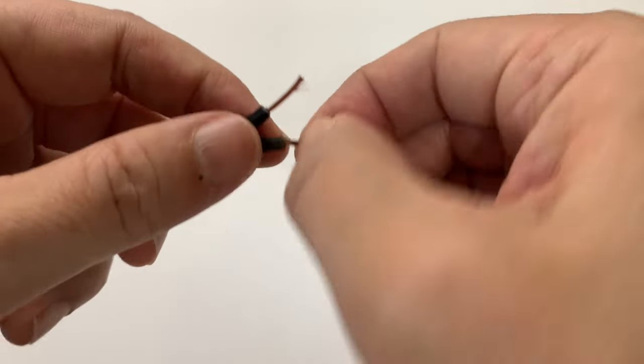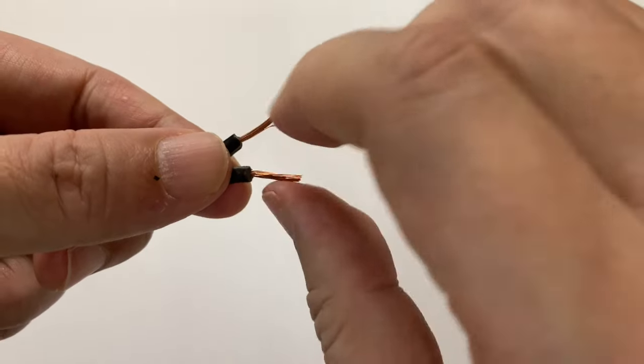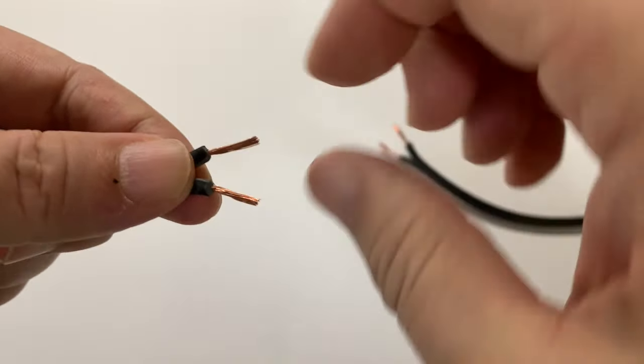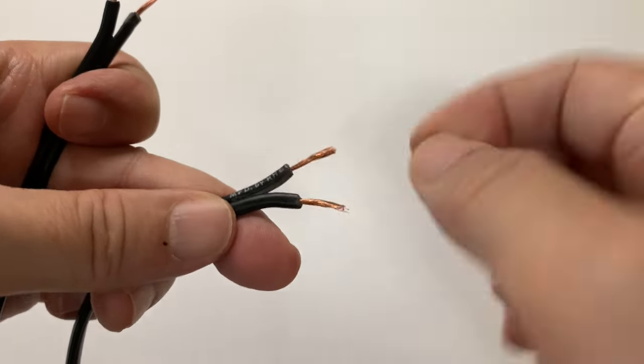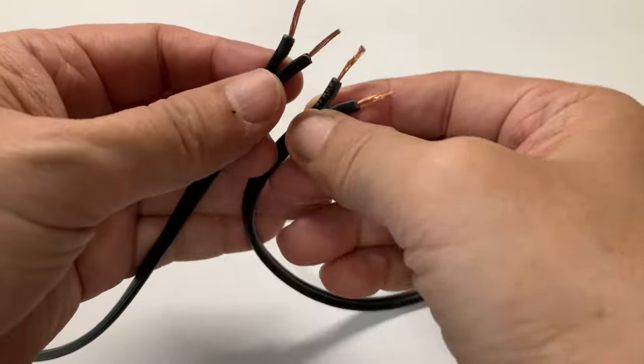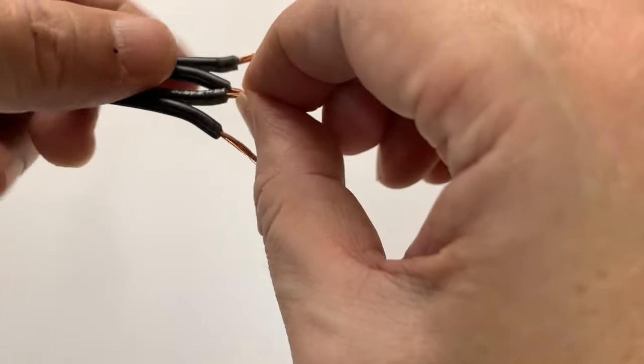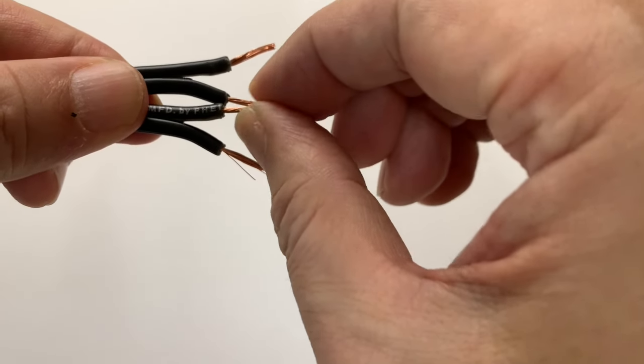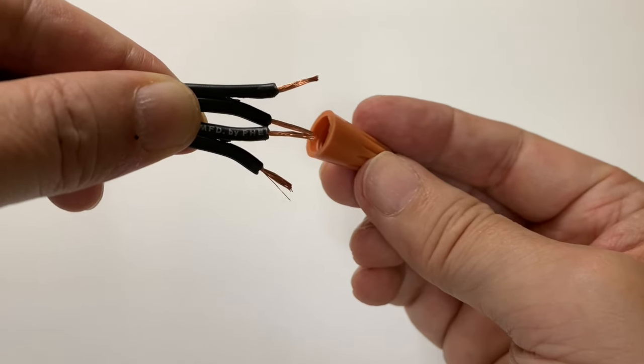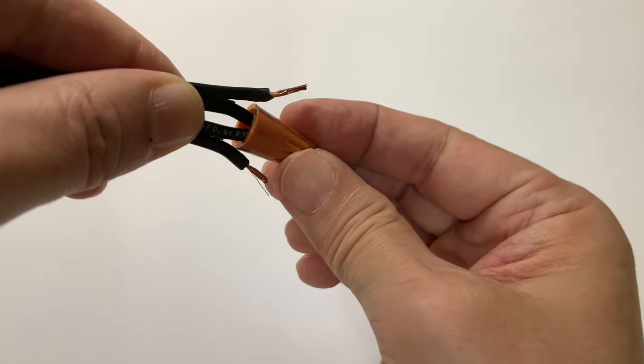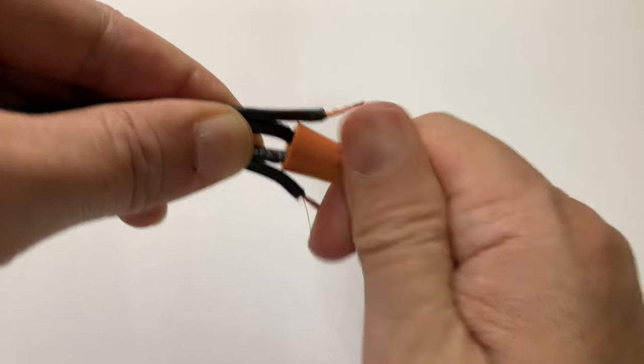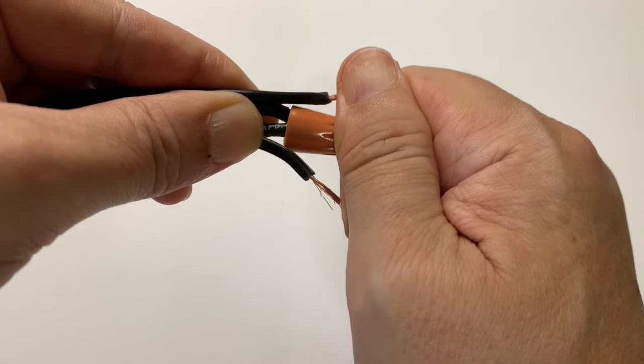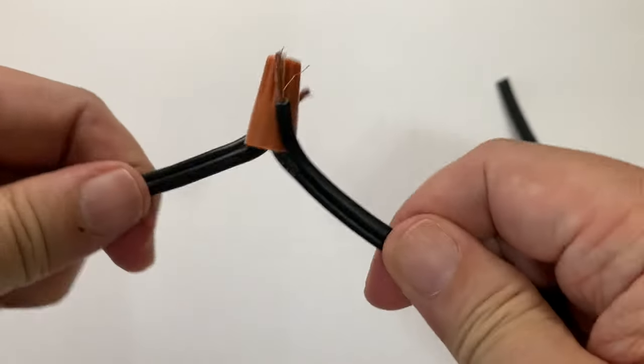For this method, you need to twist the wires a little bit, not too tightly though. Hold and align side by side the two wires to be spliced together. Do not twist them together though. Then insert them together into the twist nut all the way to the end. Then twist the nut until you feel a firm resistance preventing further twisting. Perform a pull test to be sure.